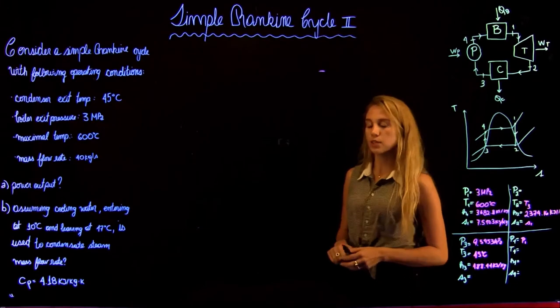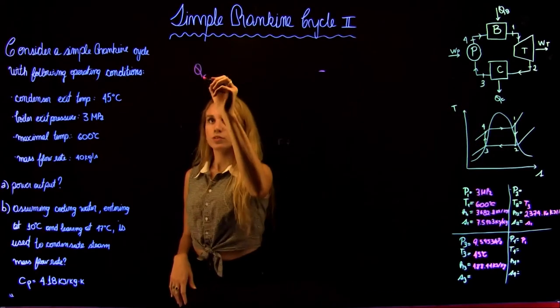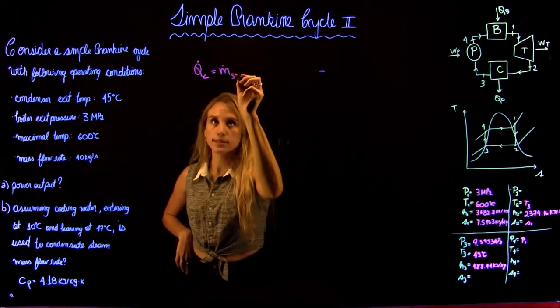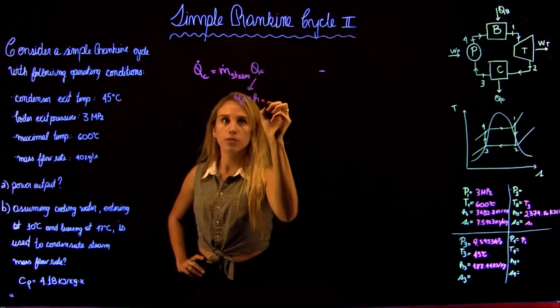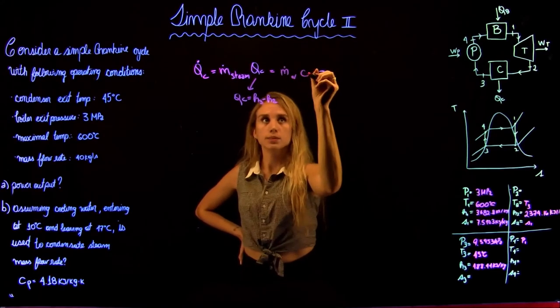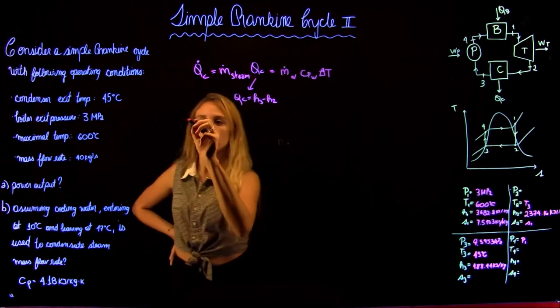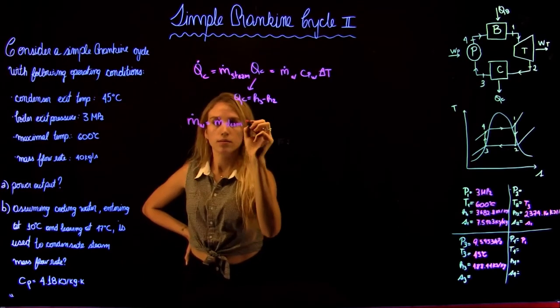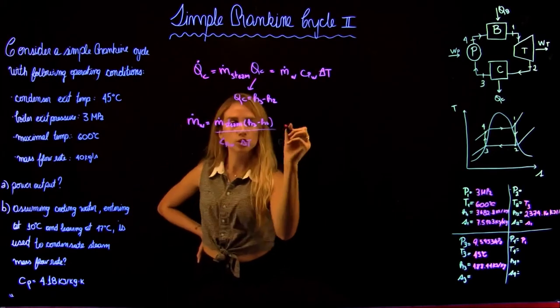Now that we've completed the first part, we jump to the second part. We go back to the energy balance on the condenser: the heat rate of the condenser equals the mass flow rate of steam times qc, where qc = H3 − H2. This also equals the mass flow rate of the cooling water times the CP of water times ΔT of water. We rearrange to solve for the mass flow rate of the cooling water: ṁ_water = ṁ_steam × (H3 − H2) / (CP_water × ΔT).